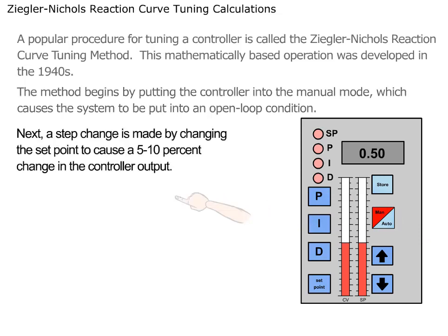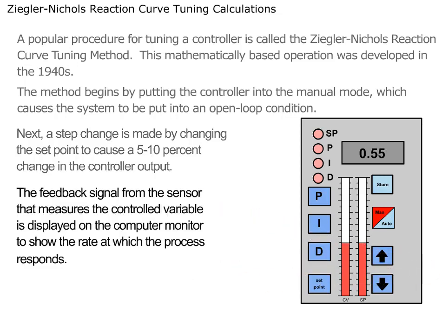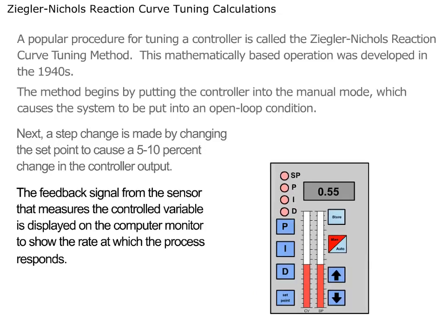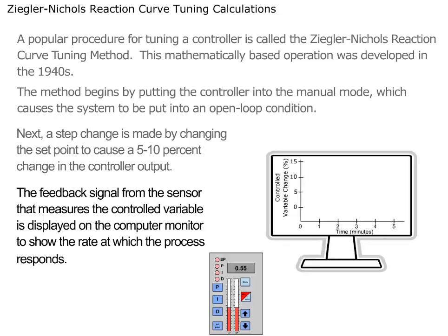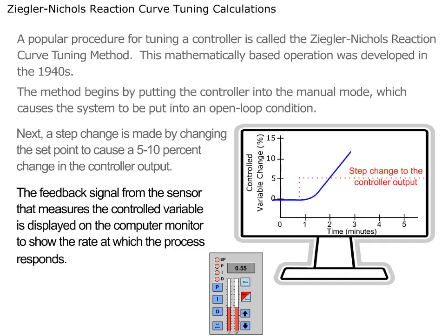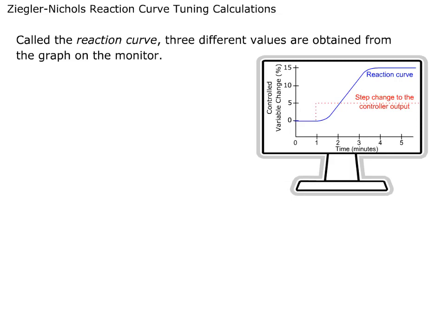Next, a step change is made by changing the setpoint to cause a 5-10% change in the controller output. The feedback signal from the sensor that measures the controlled variable is displayed on the computer monitor to show the rate at which the process responds. Called the Reaction Curve, three different values are obtained from the graph on the monitor.